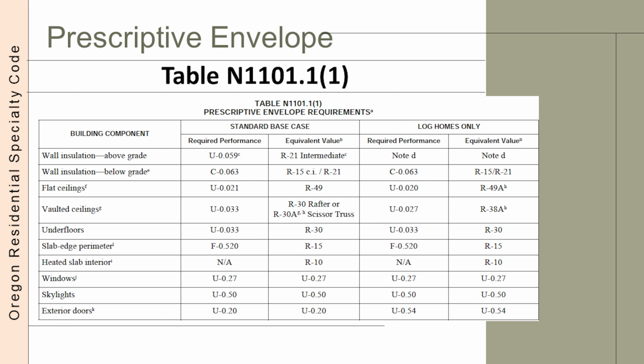For example, walls where the R21 insulation is installed between studs does not perform equivalent to R21. Heat is also passing through the studs faster than the insulation, so the effective R value of the studs and insulation combined is less than R15 for this portion of the wall assembly. One quick note, U factor is applied per square foot of assembly, which means how much energy will pass through the wall per square foot of area. Some values in the required performance column are not in square feet.